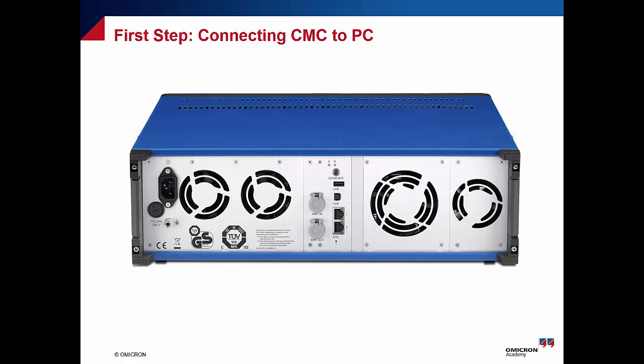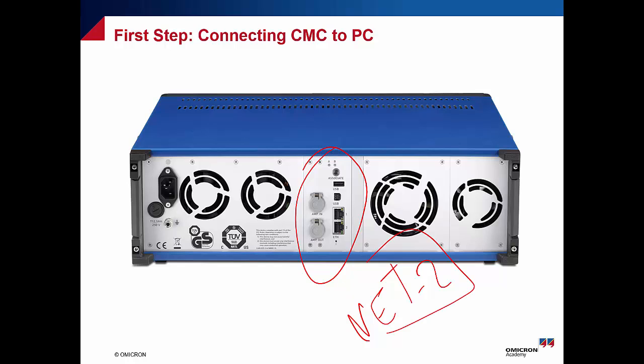Another step which is very, very important is connecting your CMC to your PC. As we see here with NET2, this is the latest technology which we have. NET2, here we have a Wi-Fi stick. If you would like to control it wirelessly, you can use it, or with a USB cable, exactly the same as the printer cable. You can also use the two RJ45 Ethernet ports, any one of them, one or two. You can connect it to your PC, and be careful about the IP address in case you have a static IP, or you can make it automatic IP address in both your PC and your CMC as well.